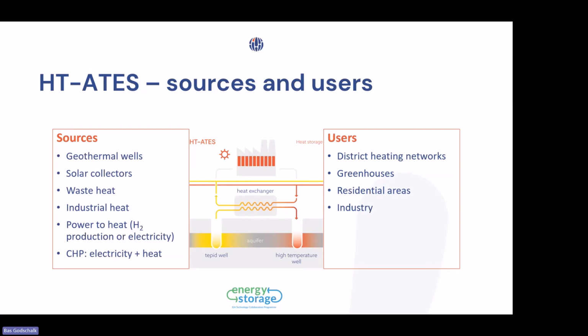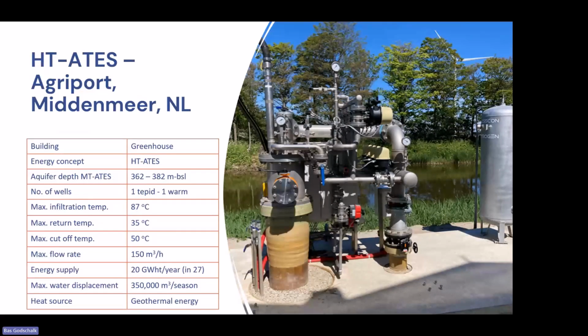There's also now a connection with the electricity network, where you can convert a surplus of electricity into heat, or another way is that you produce electricity by using CHP, and then the surplus of heat, which is produced at the same time, will also be stored in the high temperature ATES system. So in fact, it doesn't matter so much what the heating source is, but you need to take it into account when you design it. On the user side, we have all kinds of uses like district heating systems, greenhouses, residential areas, etc. Now, the example which was mentioned already is a full-scale project in Middenmeer, where we installed the ATES system at nearly 400 meters depth. And the storage temperature is about 85 degrees with a maximum flow rate of 150 cubic meters per hour.